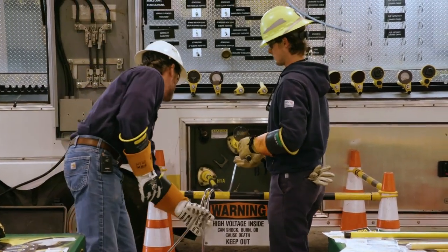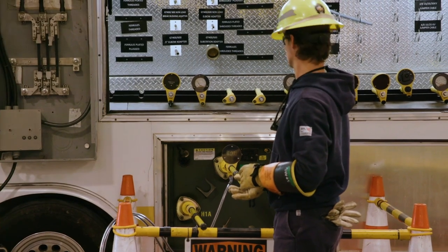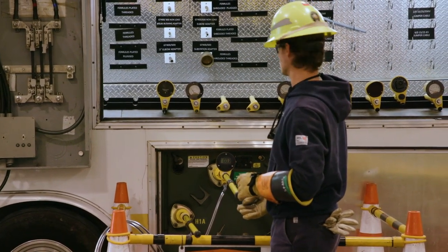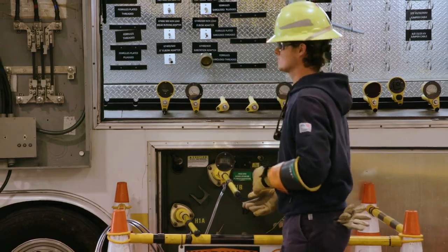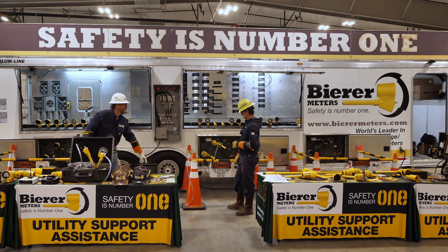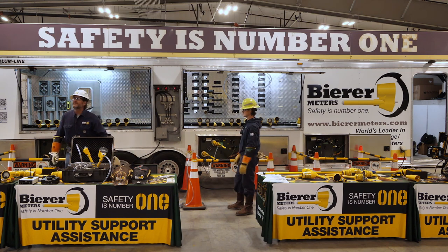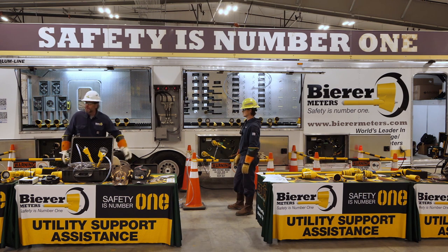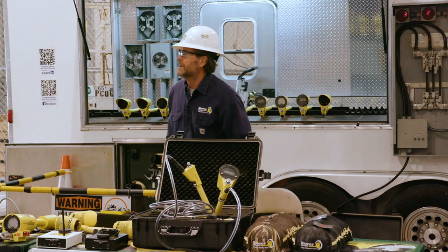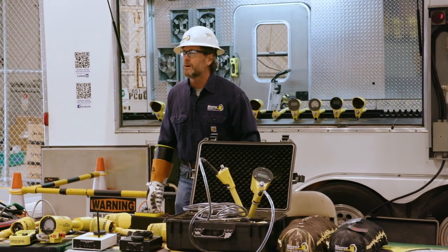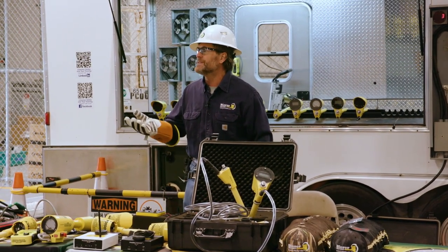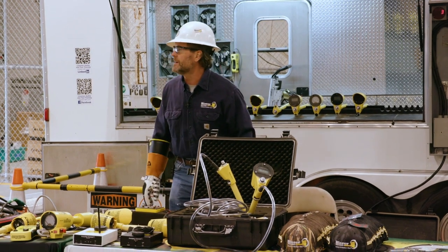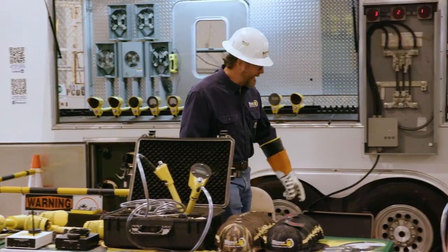Okay, what'd you get? Three? All right, so it's about 0.3? Does it say 0.3? Yeah. So there's a little bleed on that cable. Do you hear that? There's a little bleed on that cable. If that cable right now was in wet grass, you'd see a higher reading, maybe 0.6, because of the wet grass. But here the concrete's pretty dry. There might be some steel in this concrete, because normally with dry concrete we're getting closer to 1 or 2 or even 0. So I'm thinking there's some steel in this concrete, all right? And you can hear that cable buzz.